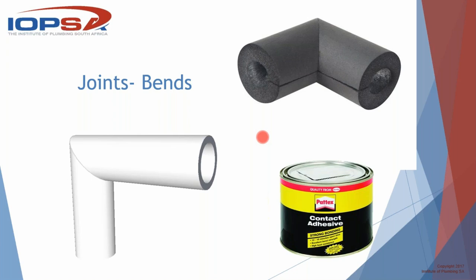But now on that handout, on the links that's on the handout, you'll find a couple of very interesting videos, and they go through how to manufacture these things off-site. So a bend like this, you'll manufacture 10 of them in your workshop with a slit there. That actually struck me as a brilliant idea. And in the next shot, you'll see a T-piece as well. It's an absolutely brilliant idea because all you need to do is slip this over all your bends. You then have a whole bunch of straight pieces to put in between, no problem. You simply glue it, and that glue joint with contact adhesive is as good as solid. It's not going anywhere. And then all that remains is to protect it if necessary, if it's outside.